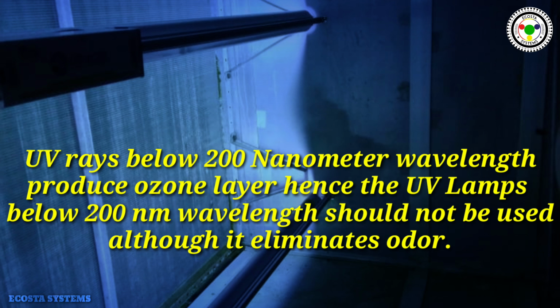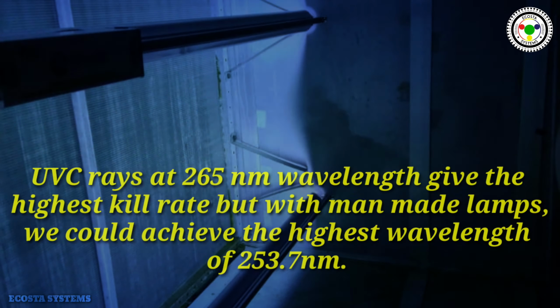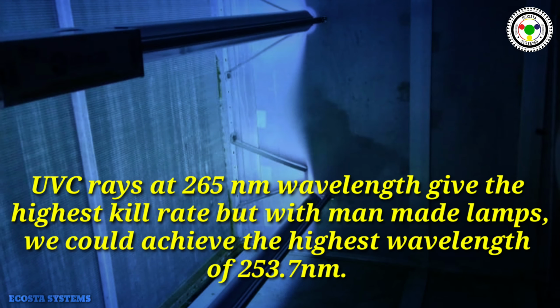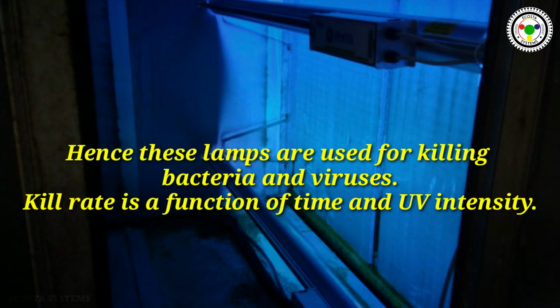UV rays below 200 nanometer wavelength produce an ozone layer. Hence, UV lamps below 200 nanometer wavelength should not be used although it eliminates odor. UVC rays at 265 nanometer wavelength give the highest kill rate, but with man-made lamps, we could achieve the highest wavelength of 253.7 nanometers. Hence, these lamps are used for killing bacteria and viruses. Kill rate is a function of time and UV intensity.